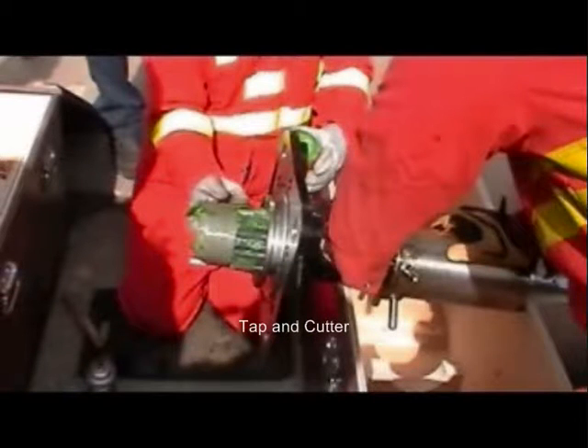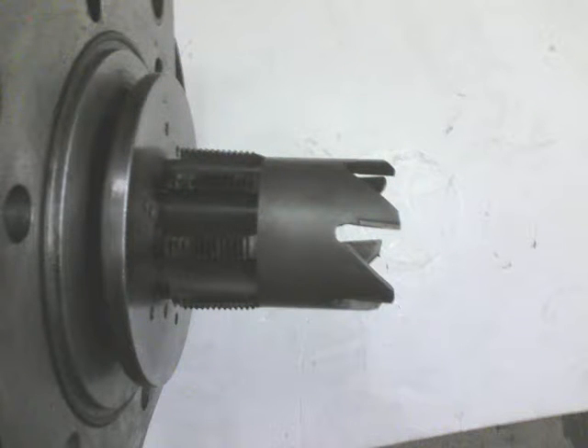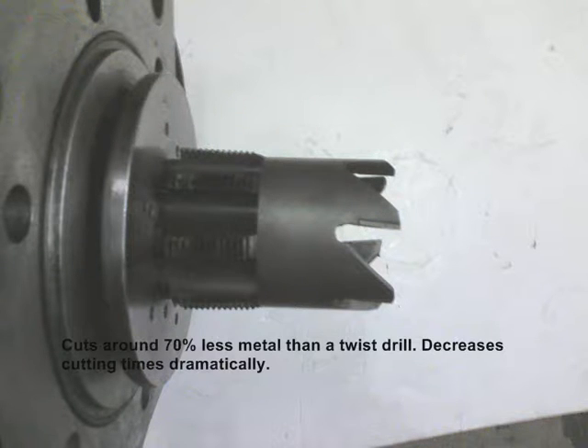the system uses a high-speed steel shell cutter and MPT tap combination that are mounted together on the keyed drill shaft, so cutting and tapping is done consecutively without having to remove the drill head.